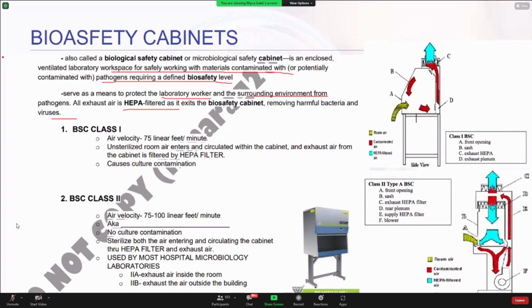We have classes of BSC. First is the BSC Class 1. The air velocity is 75 linear feet per minute, and unsterilized room air enters and is circulated. This is how Class 1 BSC looks, as shown here.